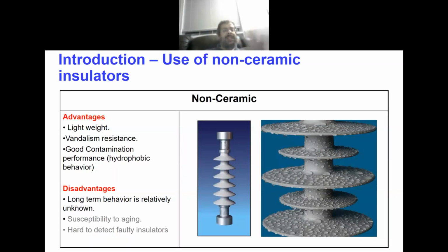More important than these two properties is the hydrophobic behavior. Because of the low surface energy of these insulators, when they are wet, the water droplets are not connected together and remain very discrete. This behavior prevents the development of leakage current.